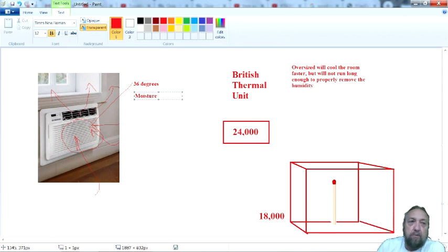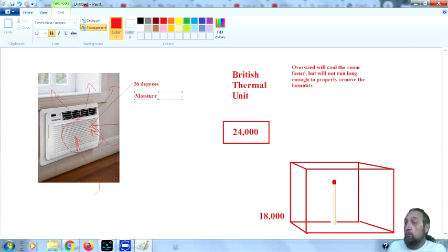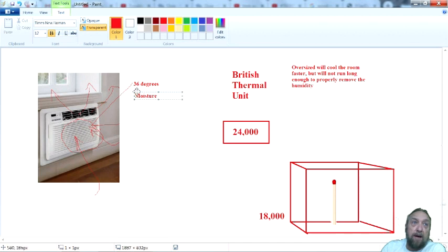Okay? So you go to the customer, okay, ma'am, I understand that it's not cooling the room properly. I'm going to make these two tests. One of the tests is I'm going to take off this front panel here and look at the evaporator, and I'm going to feel all the loops on the evaporator, the coil loops, and they should have some humidity on them, and they should all be cold to the touch. If some of them are room temperature, we have a Freon problem. Okay? But if they're all cold and wet, that air conditioner is doing its job.